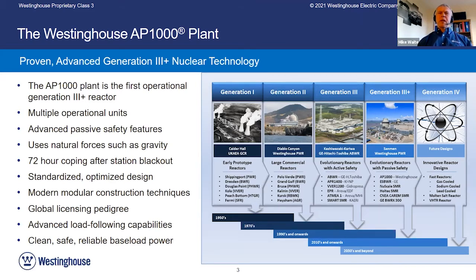Let me come back to those passive safety systems. What does that mean? It means that the ultimate safety systems use only natural forces like gravity, conduction, and convection to power those safety systems. A feature of them is that even with no AC power and no operator action, they will keep the reactor safe and cool in the unlikely event of an accident for at least 72 hours. This is what we call the coping period in the event of a station blackout.